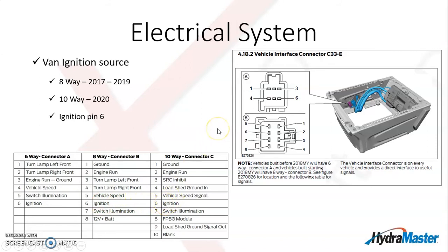So when we put the machine together, we have the plug that actually mates with this one, and we've got a wire connected to pin 6 on either the 8-way in the 2017 to 2019 or the 10-way starting in 2020. So we've plugged into that, and then we have a relay that the machine turns off and on to turn off and on the battery connection to the machine.